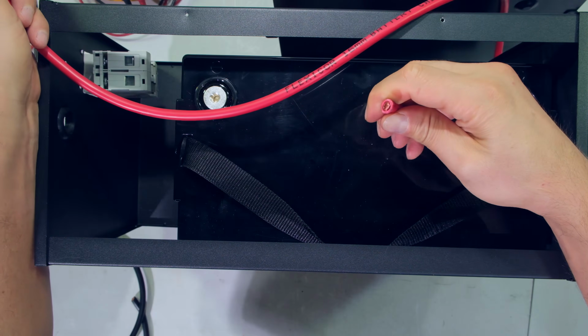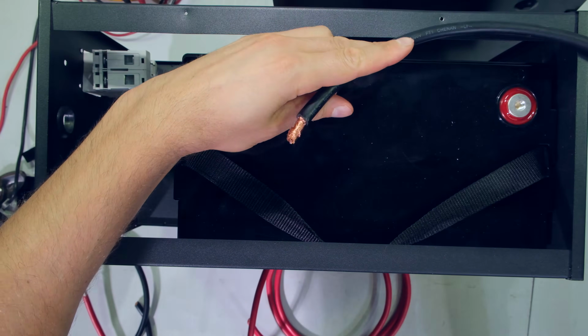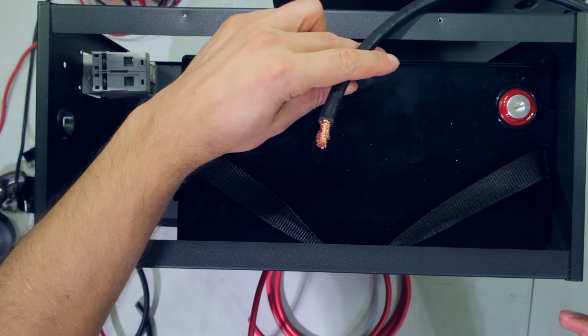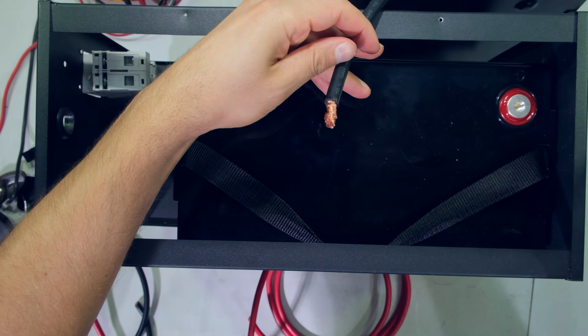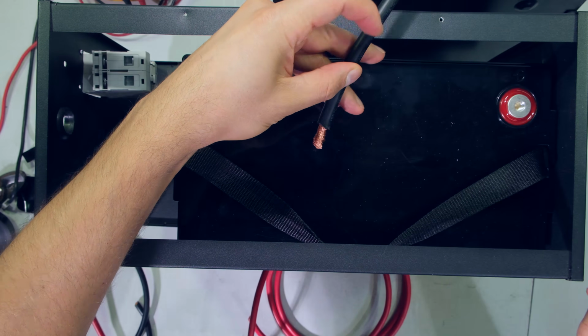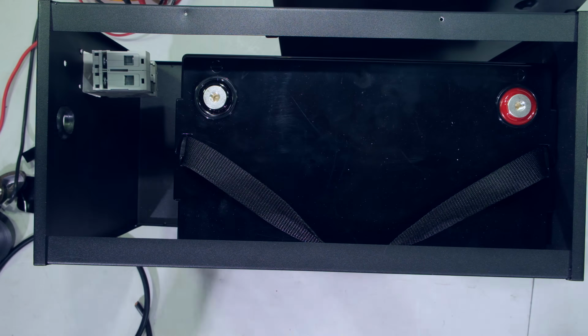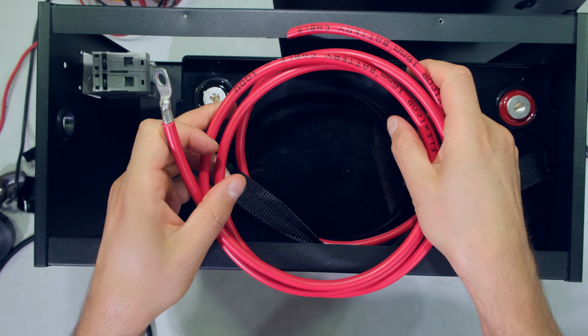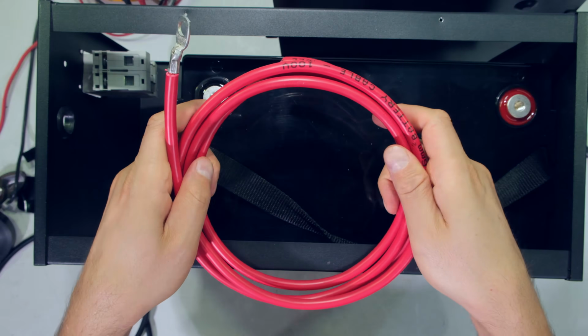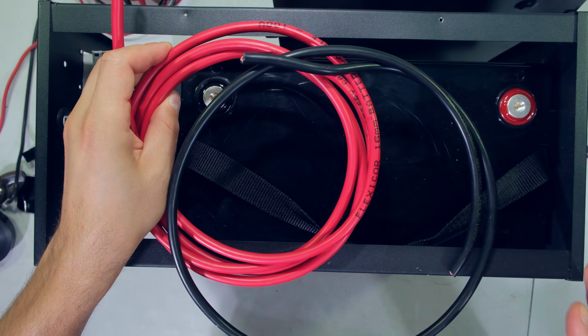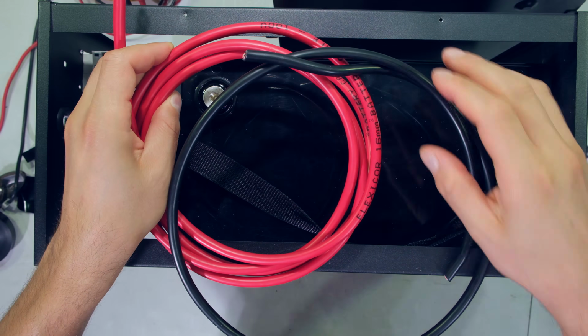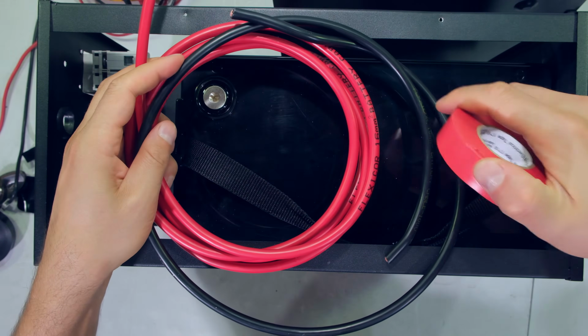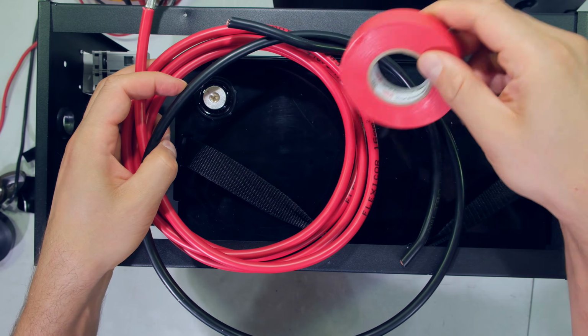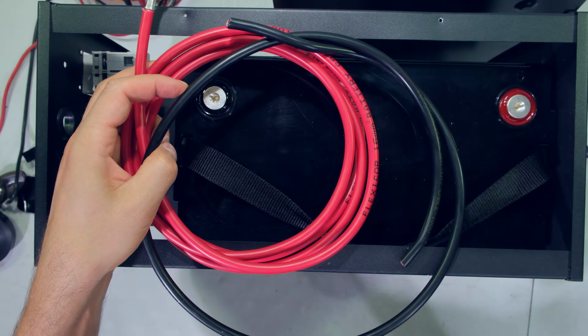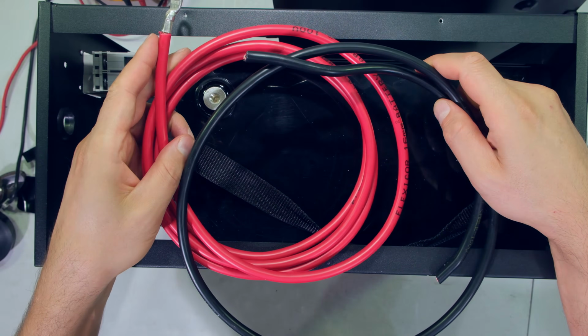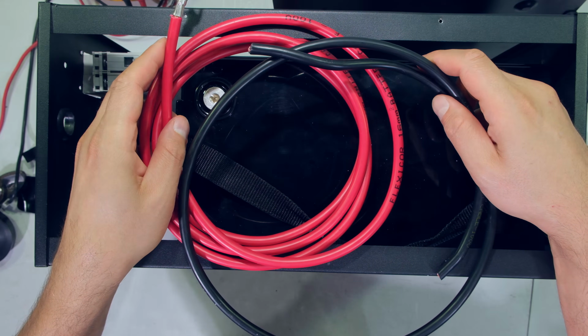All right, here is my 16 millimeter copper cable. As stated, it's actually better practice if you could use even thicker cable, because the thicker the cable, the lower the volt drop. However, technically, I can use the 16 millimeter cable, and cable is very expensive and it is a very short run. So I'm just going to go ahead with the 16 millimeter cable. Often with the thicker cables, it's quite hard to get the exact colors. So if your cable is gray, for example, you can use insulation tape to just wrap around the cable to demarcate the color. Right, for DC, black is negative and red is positive. So what I need to do now is just cut these to length.